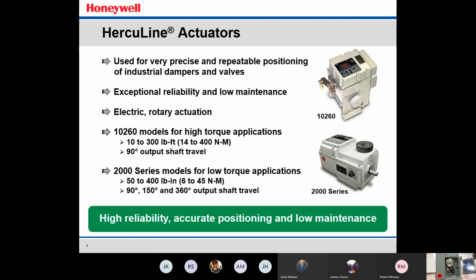The 10260 is a workhorse. You can go all the way up to 300 foot-pounds of torque. So this would be required to move large dampers, other applications that require high torque. It does also have a 90-degree output shaft travel.